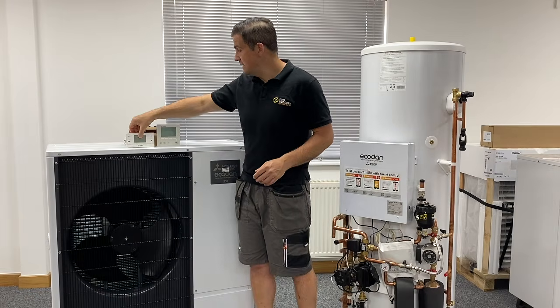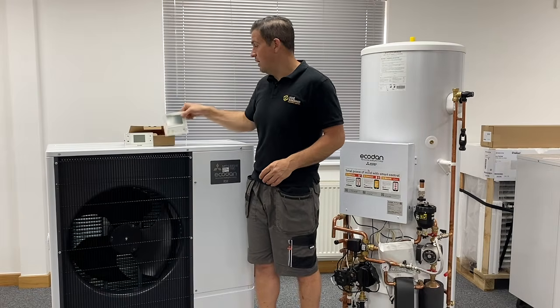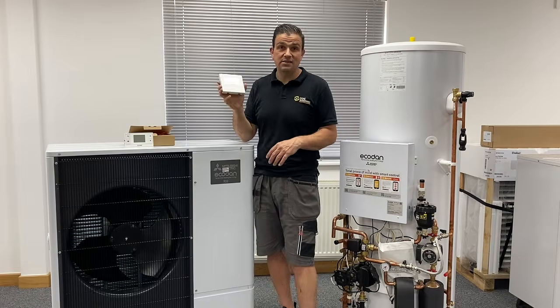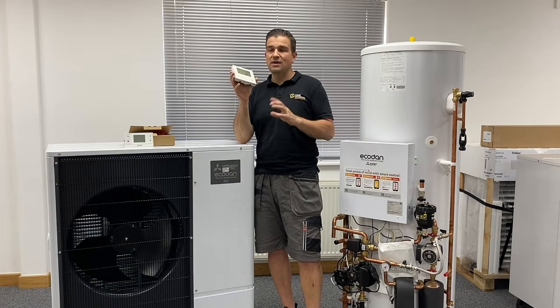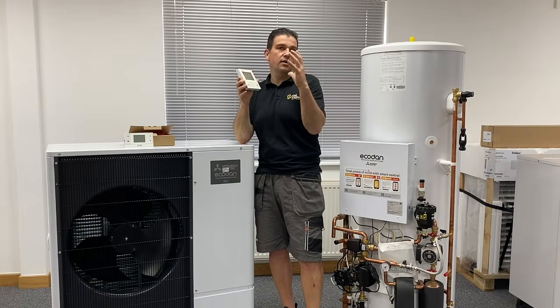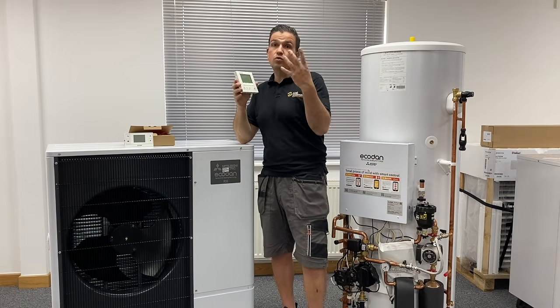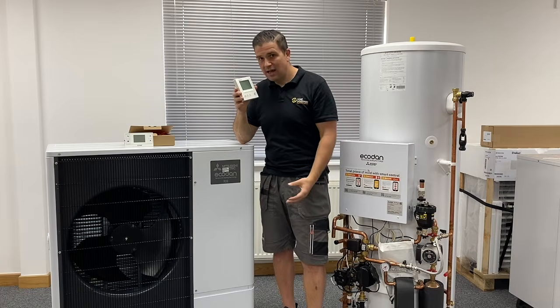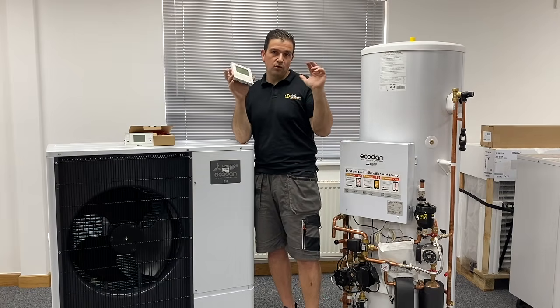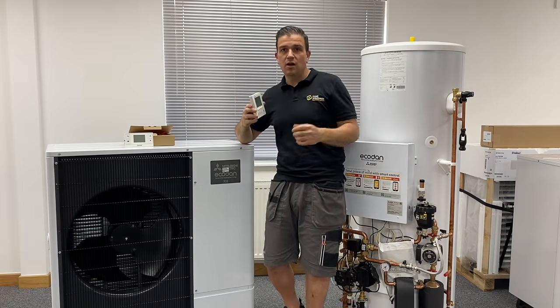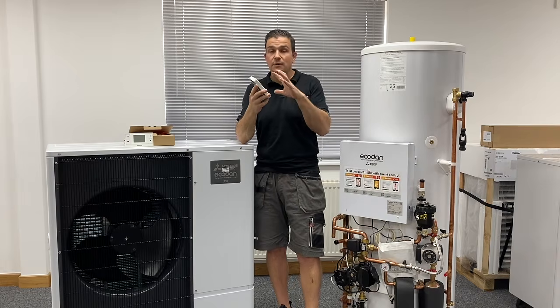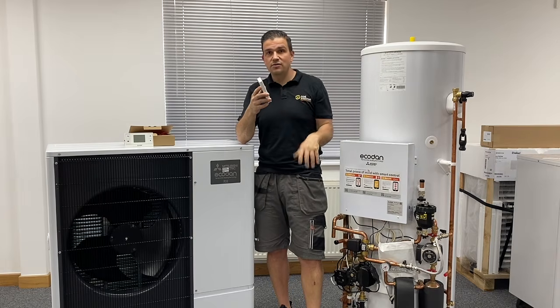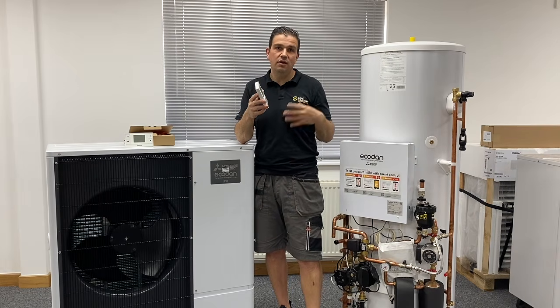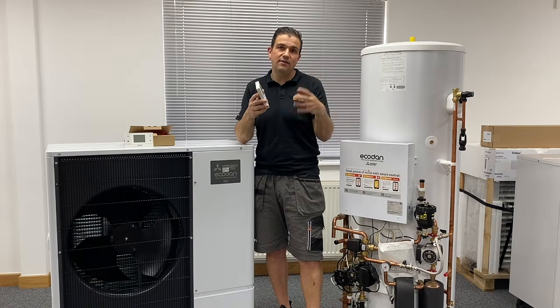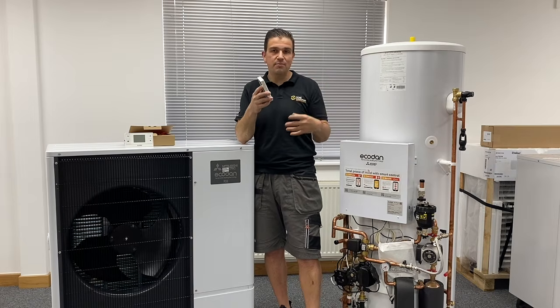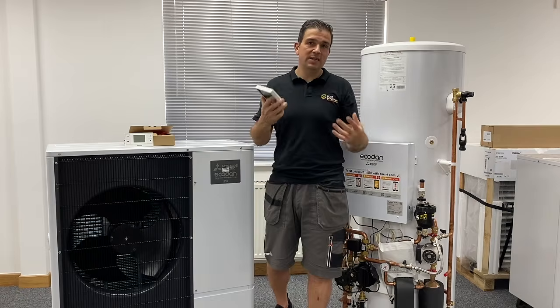And then you might see here next to it, this is basically the brains. This is the one that does all the talking. This is where we set things such as our heat curves and hot water temperatures, Legionella, which is your cycle, what they call pasteurization, whereby maybe once a week, once every 2 weeks, we'll get the temperature up to 62 degrees, have that sitting there for 3 hours or so, and then that gives it time to make sure that none of the bacteria can start forming from the Legionella.